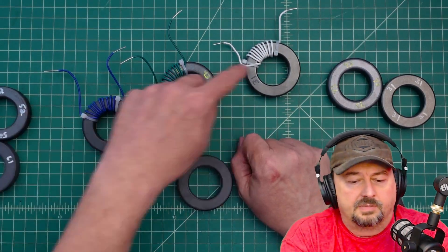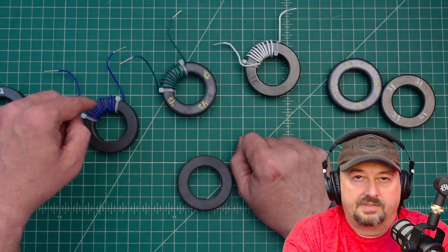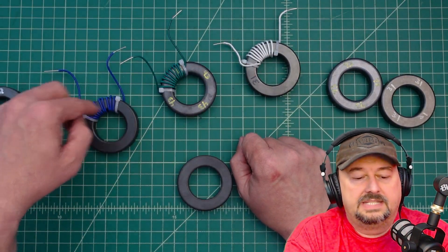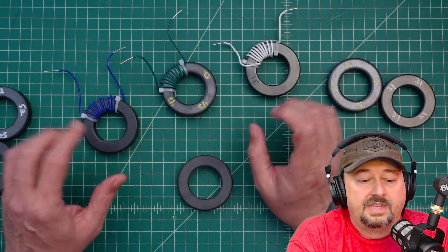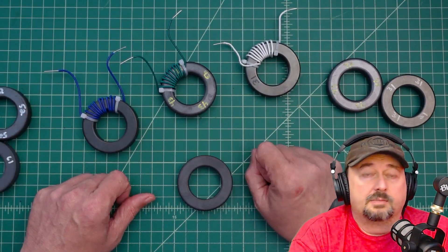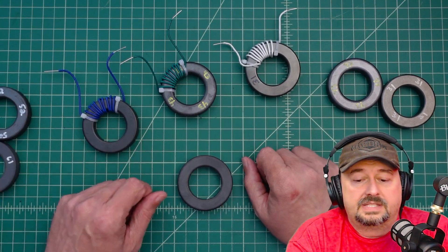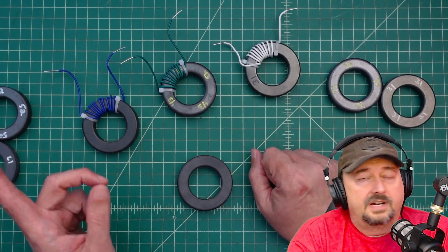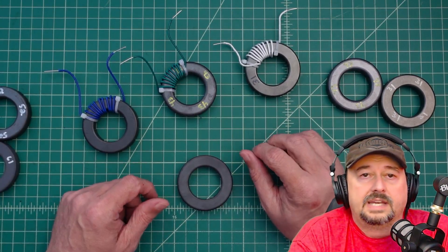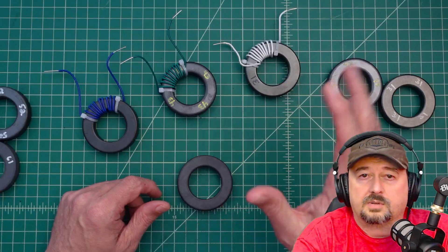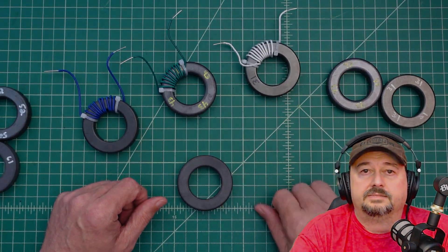The number of wraps doesn't matter that much, but it needs to be consistent across all your cores. I just picked 10 because it was a nice even number, and it's a number I've used when I've done this test in the past. Let's fire up the spectrum analyzer and take a look at it. We're going to use computer control for it, so it'll be easy to see.